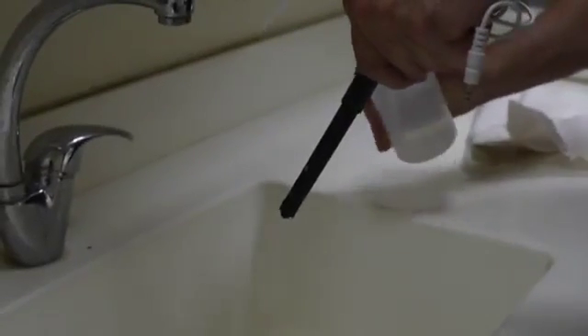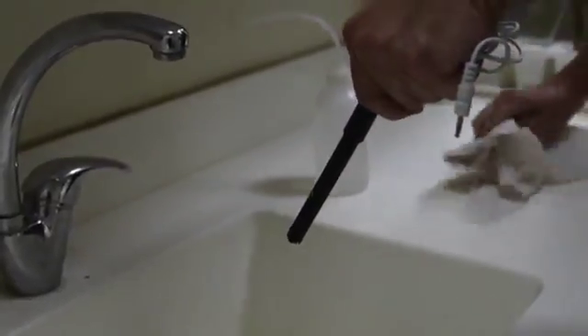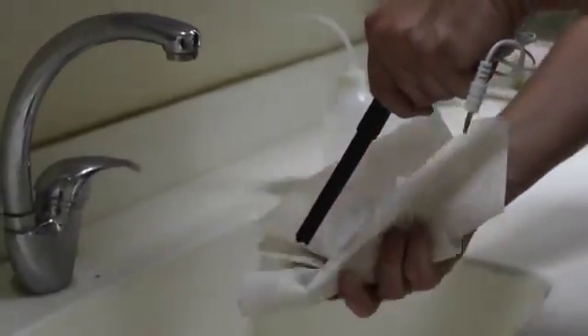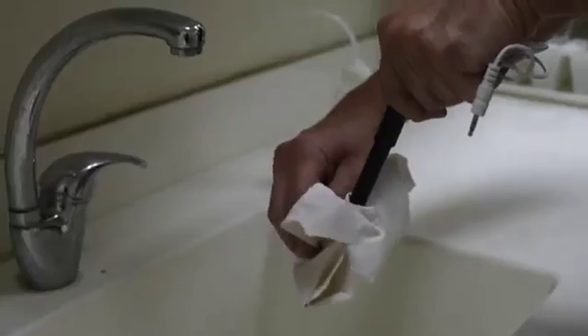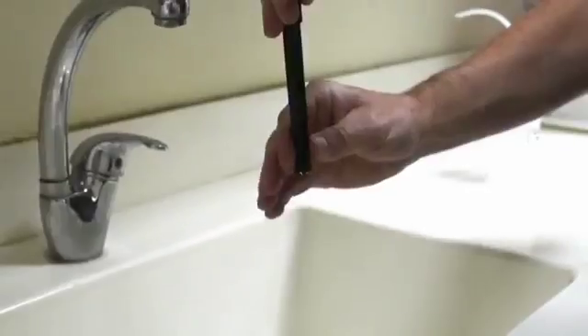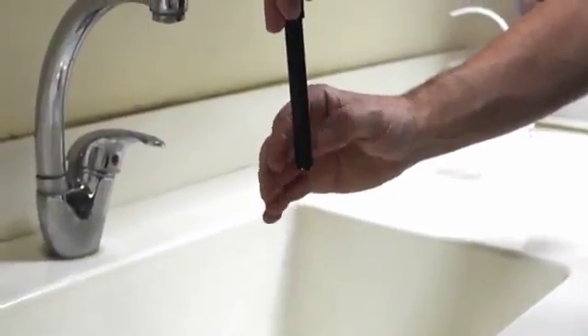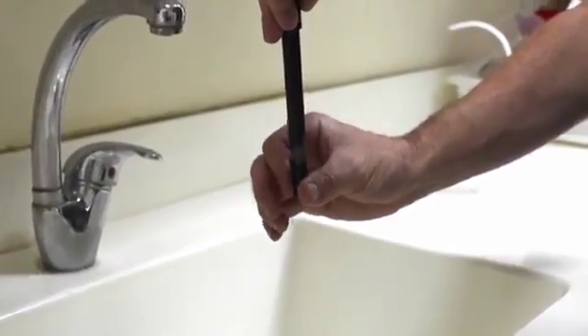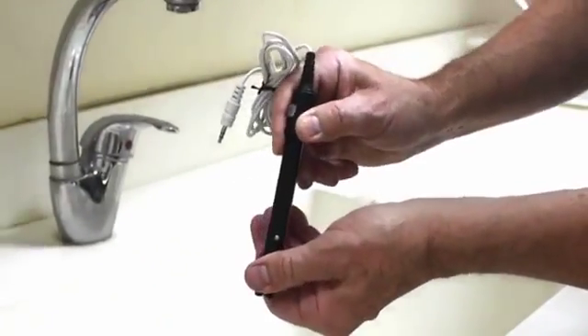After taking a sample, rinse the electrode with distilled water. Blot dry. When storing the sensor for a short period of time, up to 2 weeks, you can store it in the galvanic solution. For long-term storage, unscrew the cap, pour out the galvanic fill, screw the cap back on, and store the sensor.